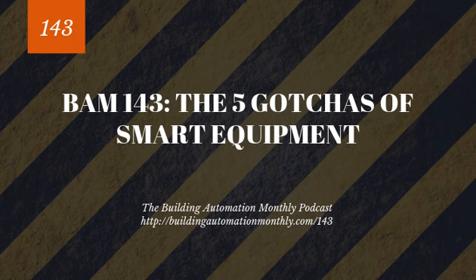This is where you have a packaged air handling unit, and you're going to control the fans with your freely programmable controller, and then you're going to let the packaged air handling unit control the cooling coil. And the two systems are not even often talking to one another, yet the process loops inside them are completely dependent on one another. If you are improperly supplying airflow, then it doesn't matter if you're at discharge air set point. And if your discharge air set point's all hosed up and you're not properly controlling your coil, it doesn't matter if you're providing the proper flow to the space. And if there's no way for these control loops to talk to one another, things can get ugly really, really fast. So gotcha number 4 is system segmentation.